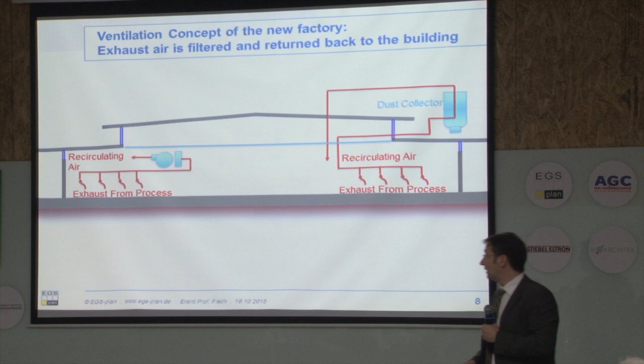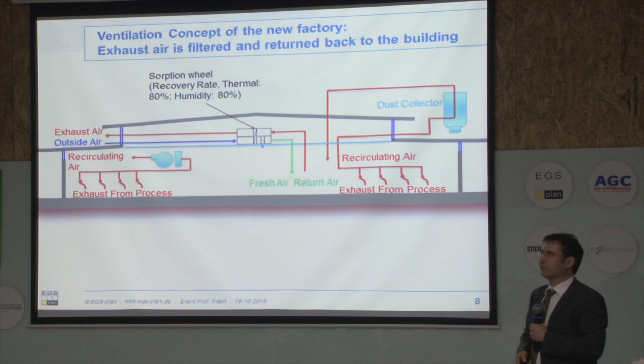However, you must know that we have a total of 3,500 workers in that factory, so we need a lot of fresh air to keep them healthy. And therefore, we have designed a fresh air ventilation system. And that fresh air ventilation system has a so-called energy recovery wheel, which reduces the ventilation energy demand by around 80%. So it's not only transferring cooling energy to the supply air, but also pre-dries supply air. So, a very efficient system in comparison to the old factory.